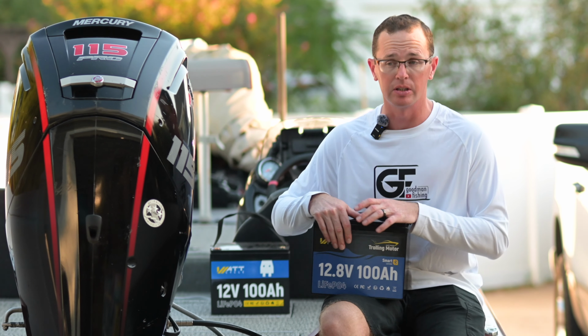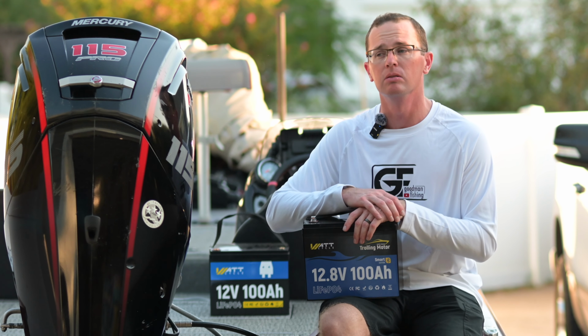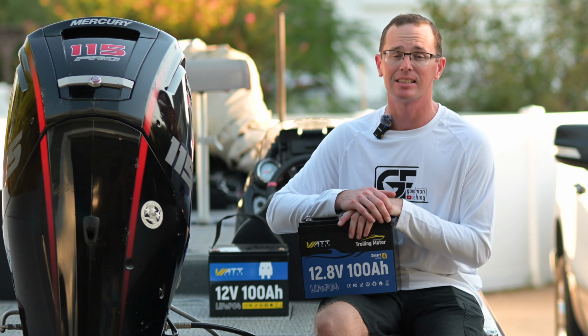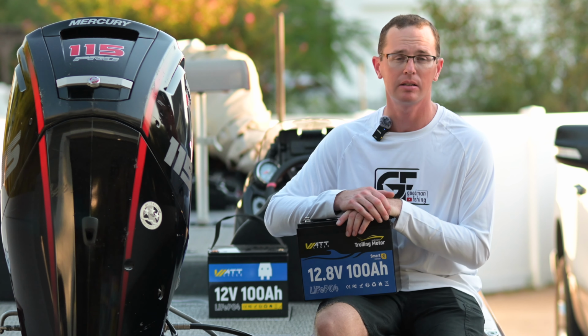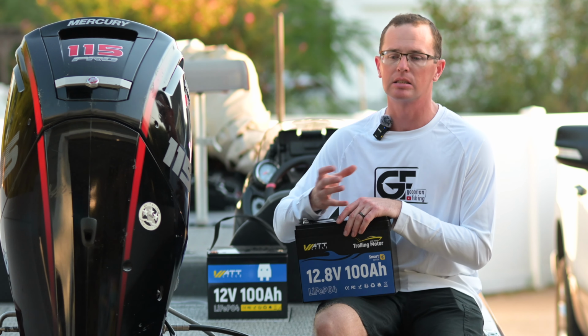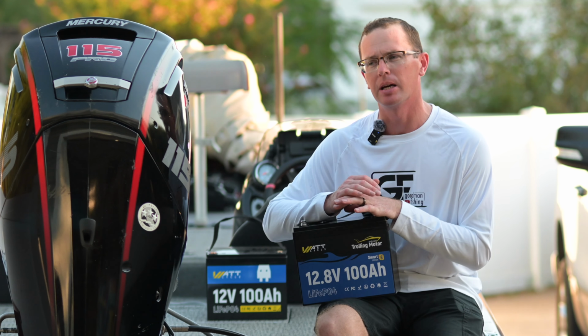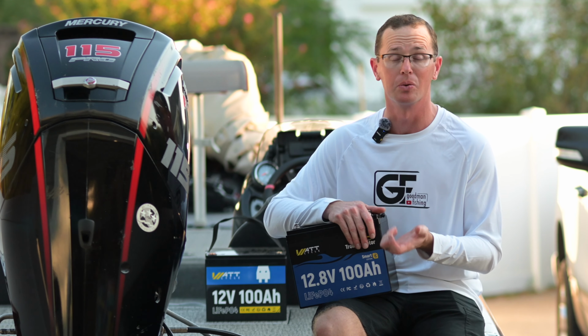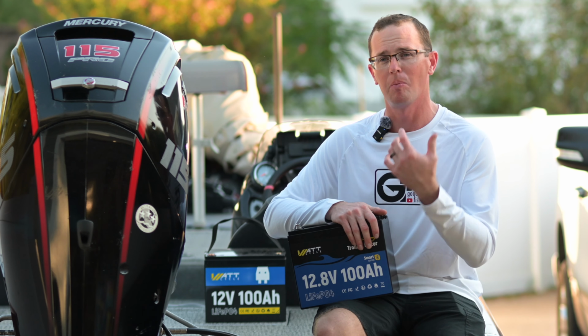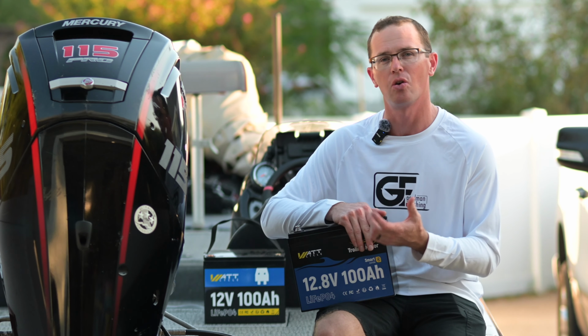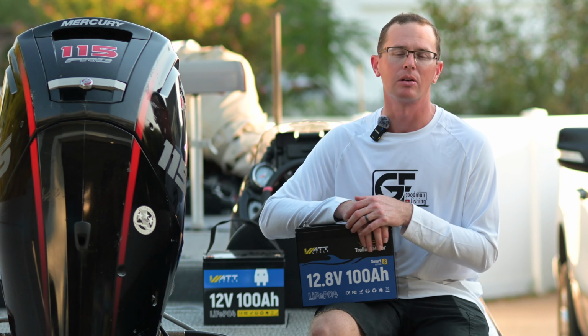If anything is going to short, you want to make sure you have your fused links in the system. It would be nice if it functioned, but this isn't the only one I've run into. I've tested several batteries with that exact same test. Some of them pass, some do not. I think that's just something they're going to have to work through. I'm not exactly sure what to tell you. The app says 140 amps, so the battery's BMS knows that it's over, so perhaps that's something they're getting ironed out.